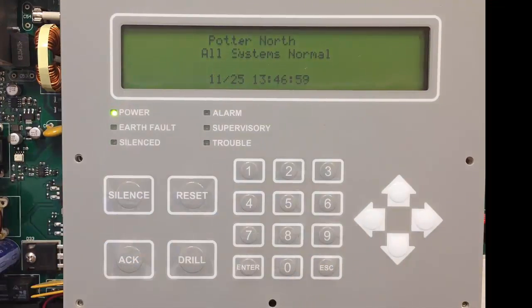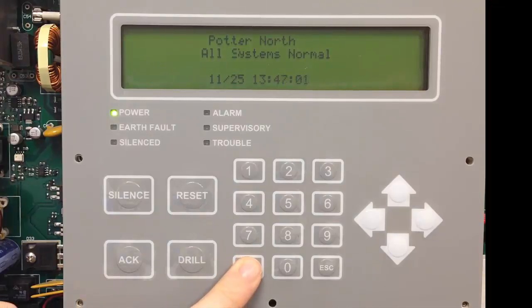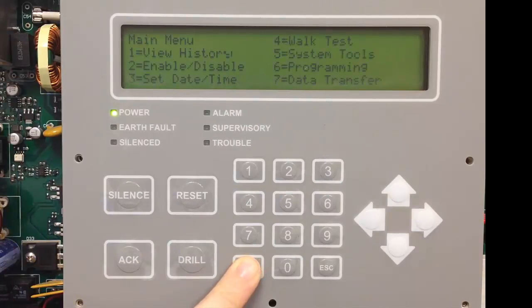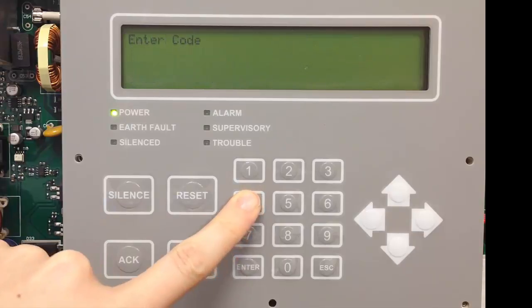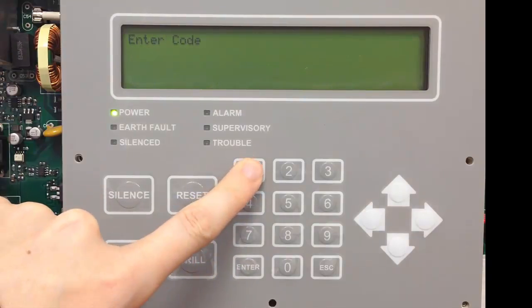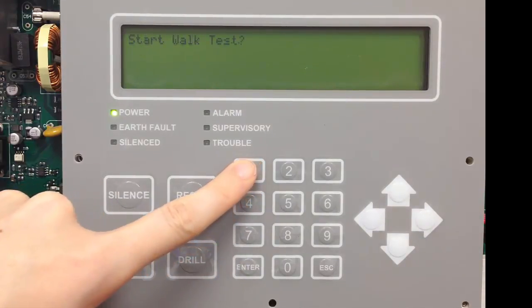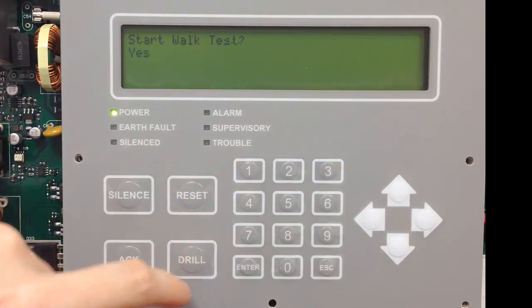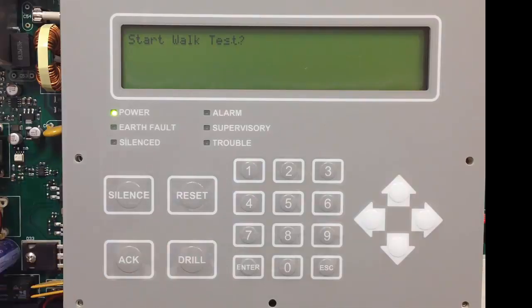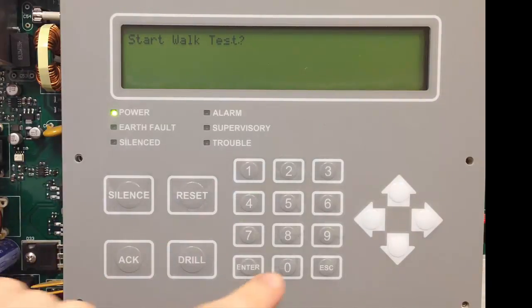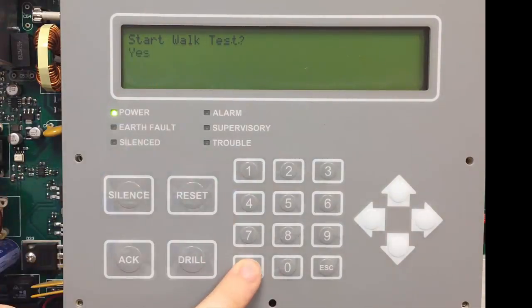At this point you can start walk test from the fire alarm control panel. Access the main menu, select option 4, walk test, enter the code. Your first option is to start walk test, so you want to say yes to this, which is what is flashing, so select enter.